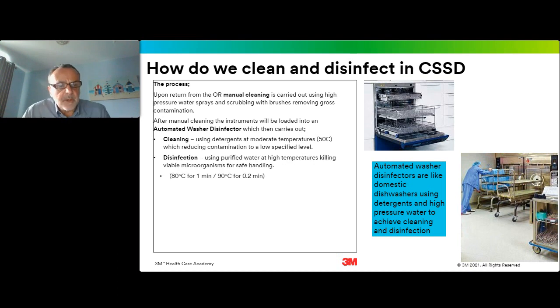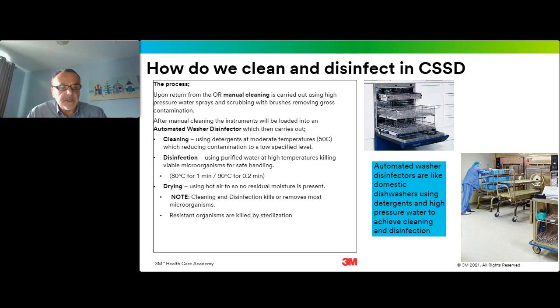The next step would be thermal disinfection, and in this stage, purified water would be used at high temperature in order to kill the microorganisms, typically maybe 80 degrees C or 90 degrees C water, using, as I say, ultra purified water. And then the final stage is, of course, drying, and this tends to use hot air, so that at the end of the process, no residual moisture is present on the instruments, and so they are then safe to handle by the operators, who will then inspect them and repackage them ready for sterilization.